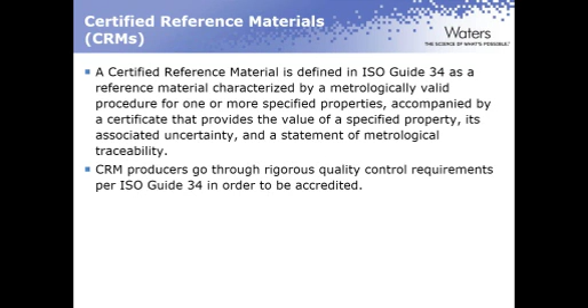And that goal is to not only get us accredited to 17025, but just as importantly, keep us accredited to 17025. So, certified reference materials, or CRMs. Well, what are they? A certified reference material is defined in ISO Guide 34 as a reference material which is characterized by a metrologically valid procedure for one or more of the specified properties, accompanied by a certificate that provides the value of a specified property, its associated uncertainty, and a statement of metrological traceability. CRM producers go through rigorous quality control requirements per ISO Guide 34 in order to become accredited.